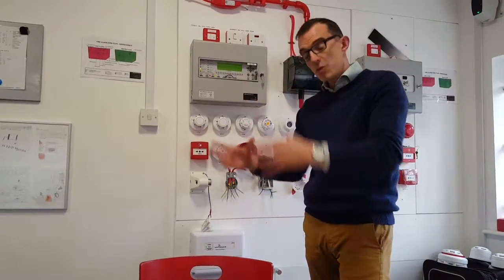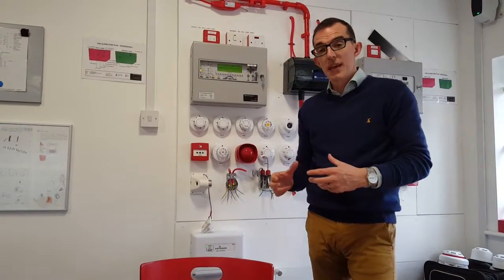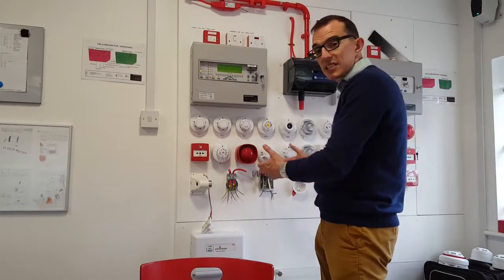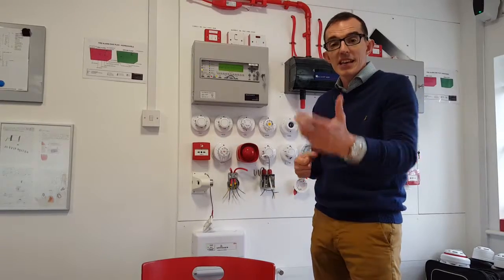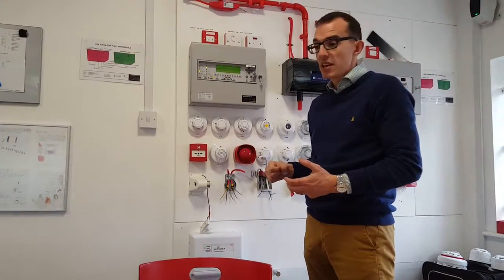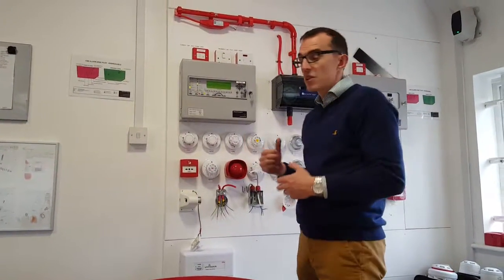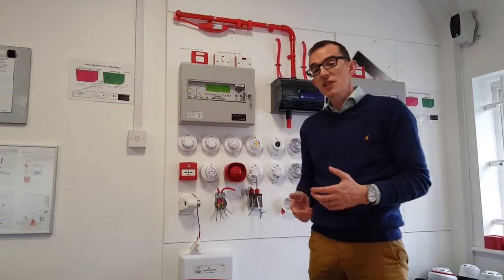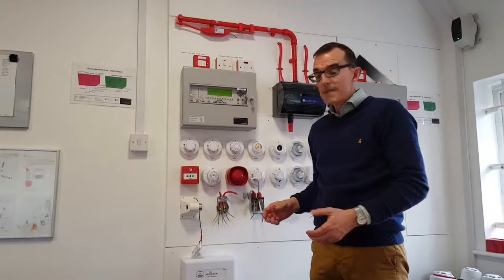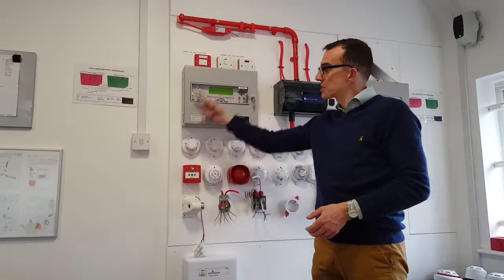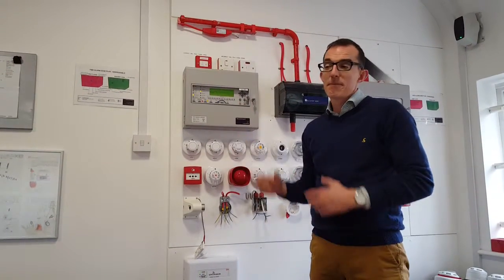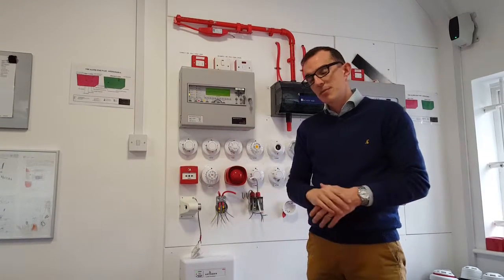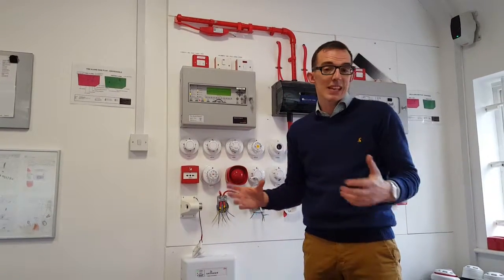But the actual routine servicing of a fire alarm system is to check that the whole thing works by using different bits of kit: smoke for smoke detectors, heat detectors for heat detectors, flame detectors, and associated bits of kit for high level detection, and prove all of that works, activate the system, prove that the system does what it's supposed to do, and make sure the system is looking after the building, protecting the building, and protecting the people in the building. And that's fundamentally it.